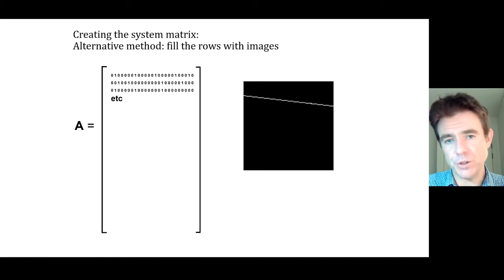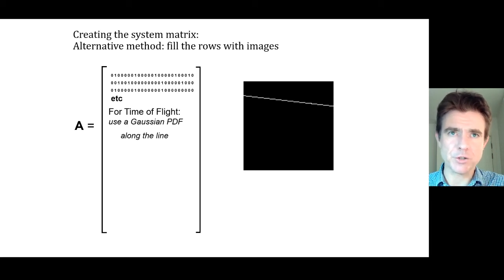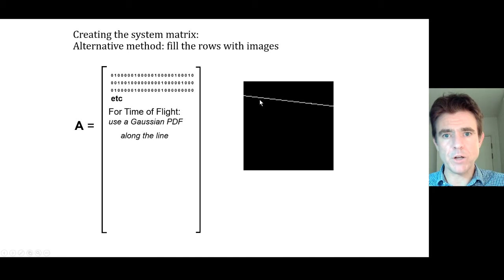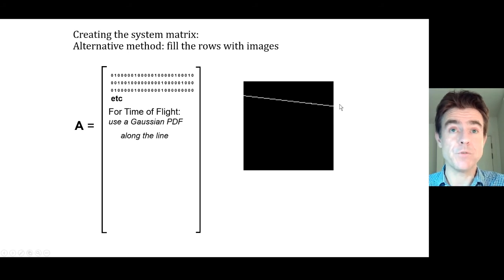You can consider all the various lines of response through the scanner field of view, and that's how you populate the rows of a system matrix for doing a discrete X-ray transform. System modeling is extremely flexible. For example, if we had time-of-flight information for the PET photons, we could just do a Gaussian probability density function along that line. Instead of being a solid line with roughly the same value throughout, according to the arrival time difference we could have a Gaussian-modulated weighted integral along the line, and that would model the time-of-flight data.